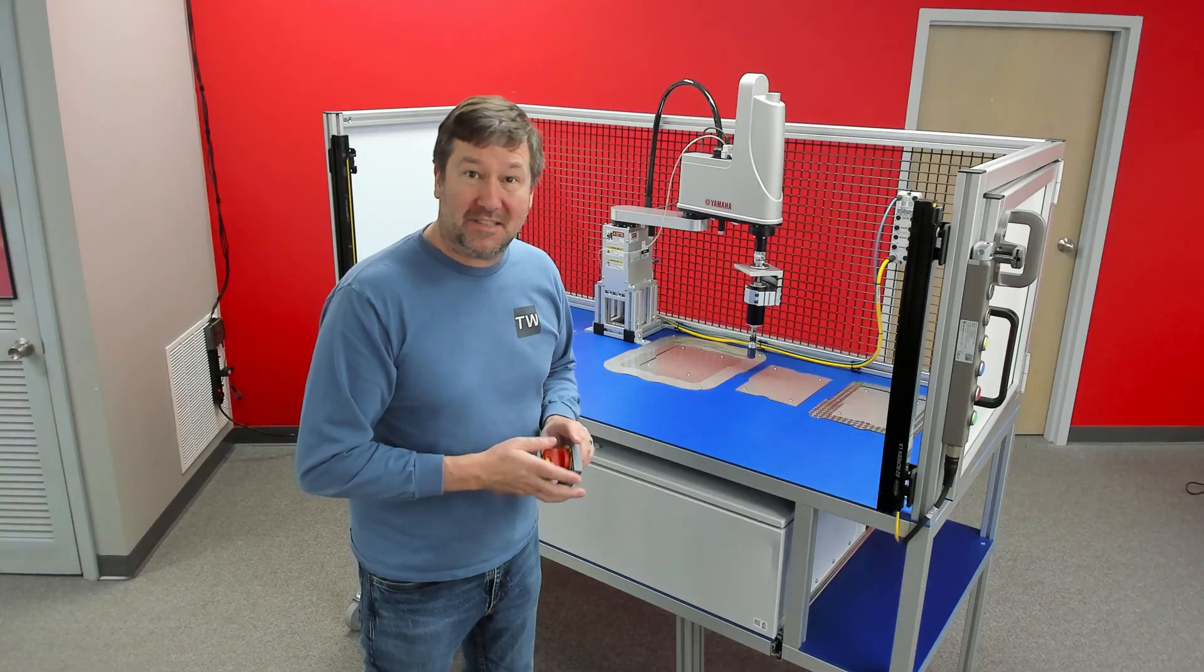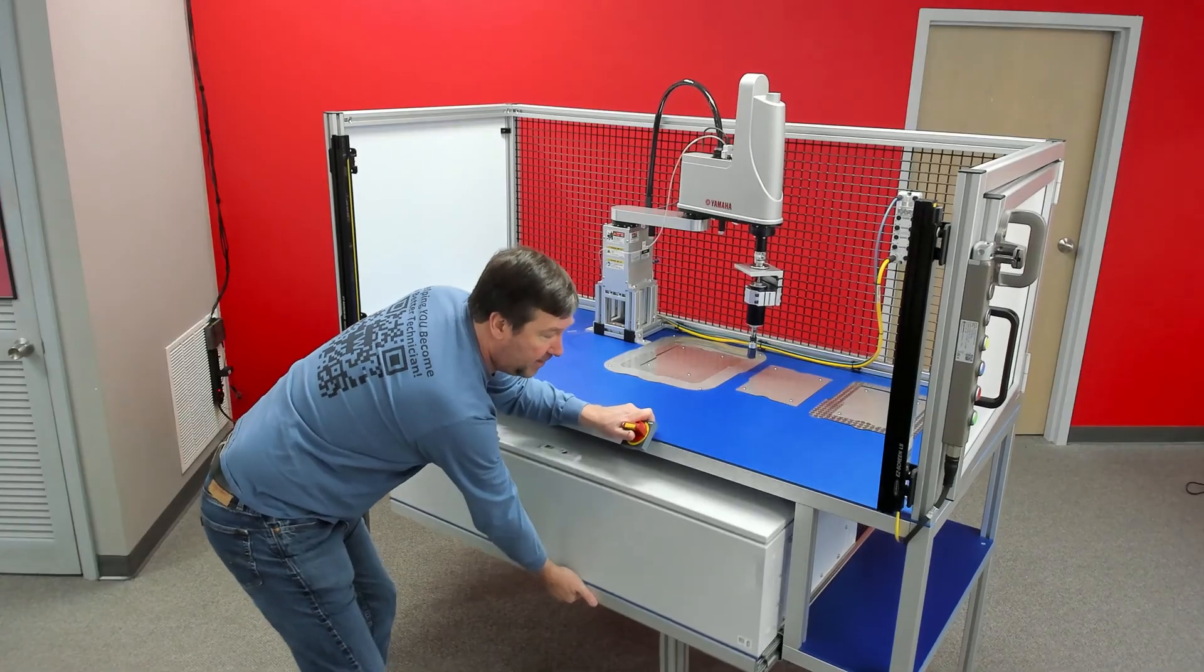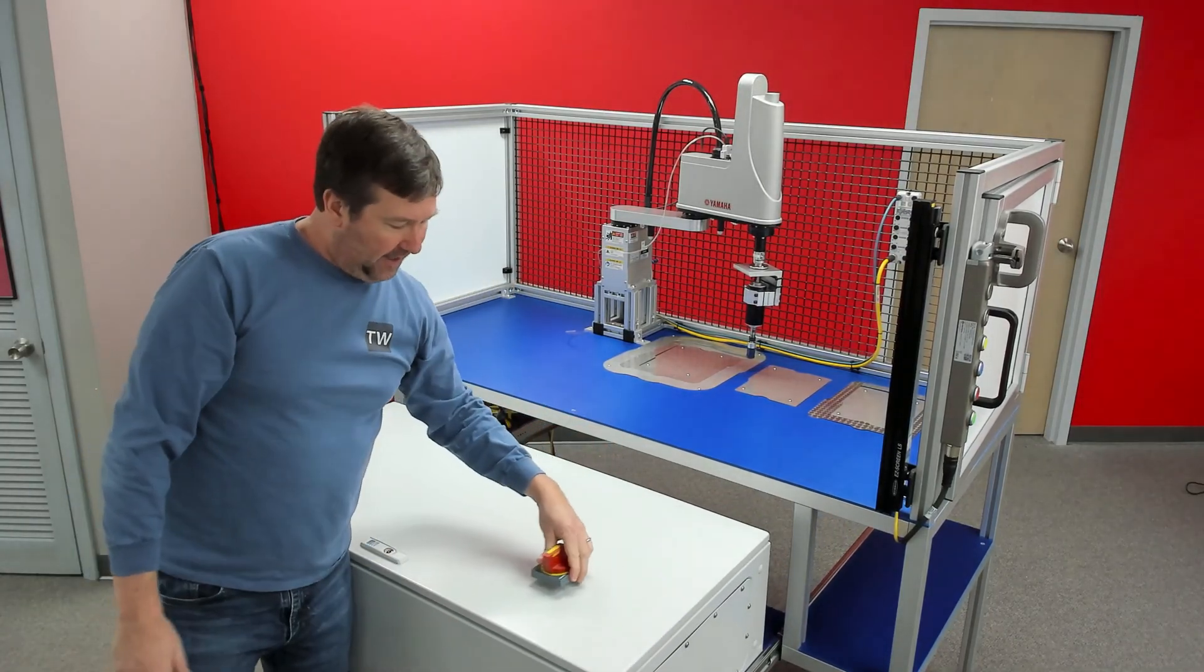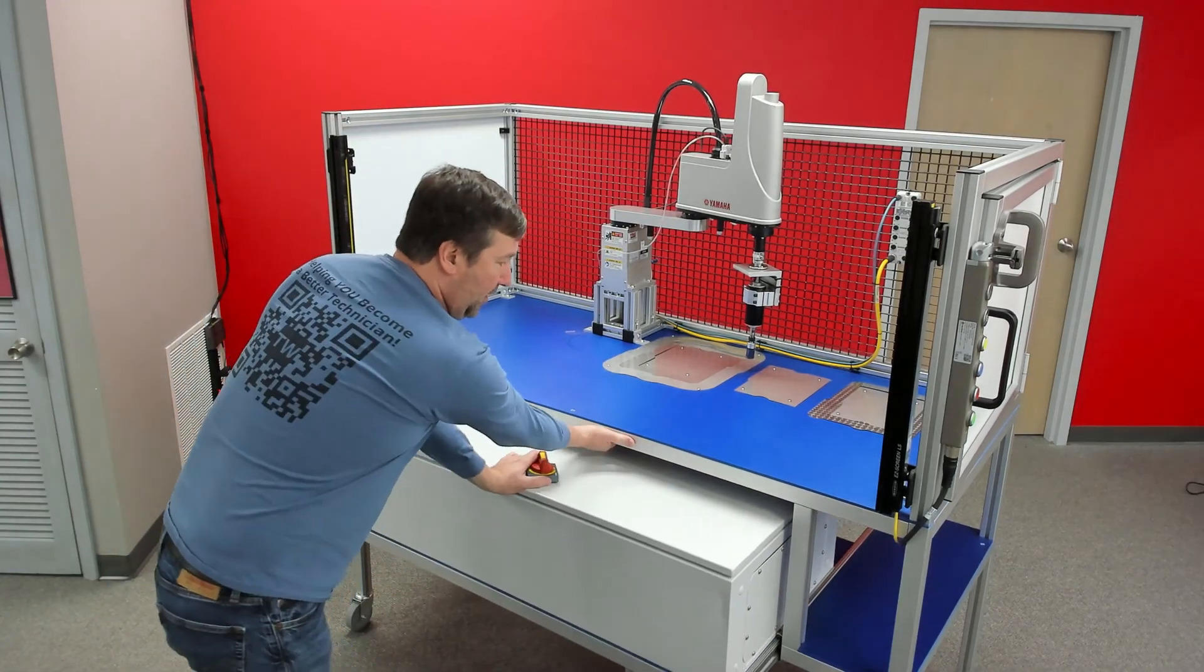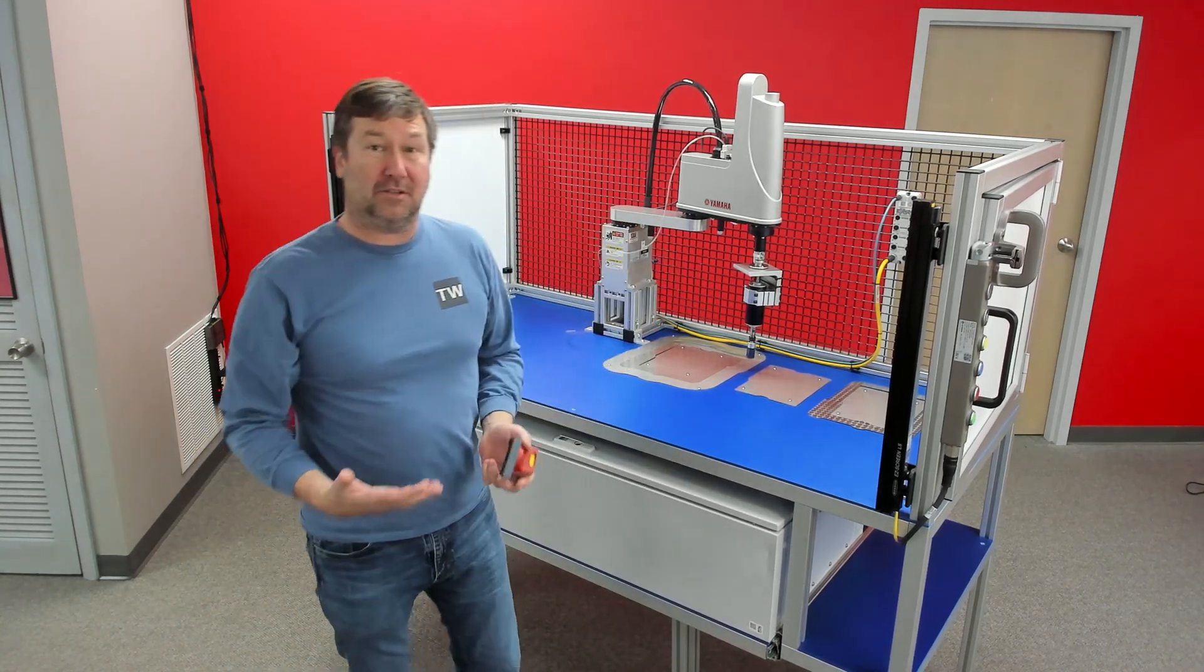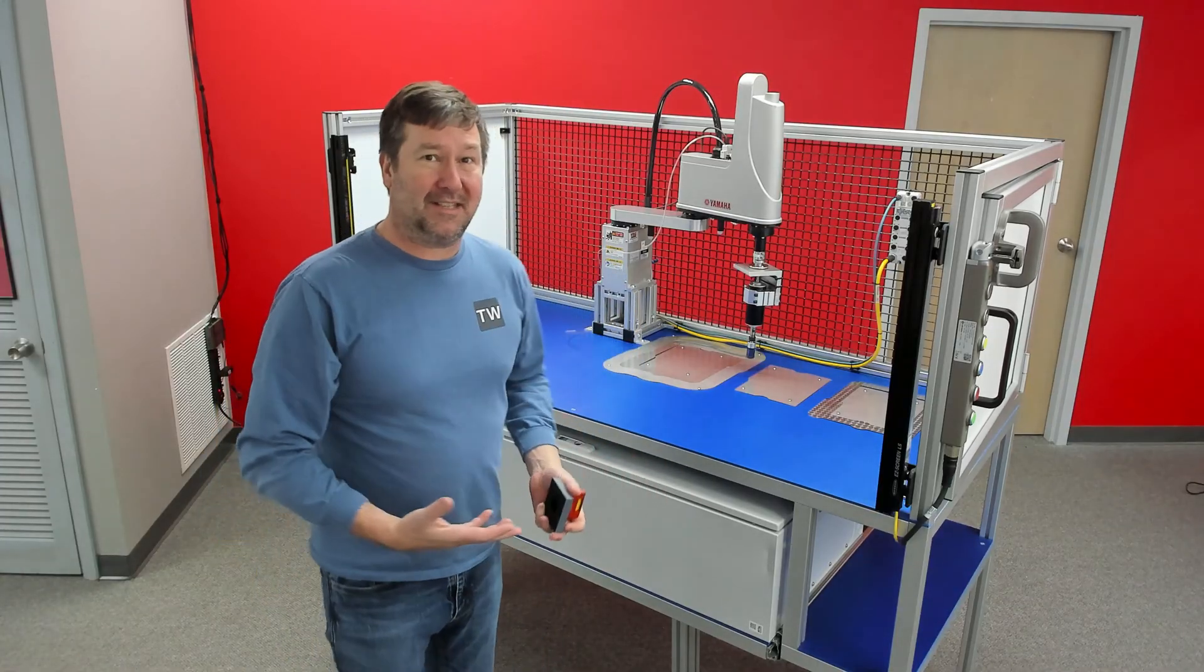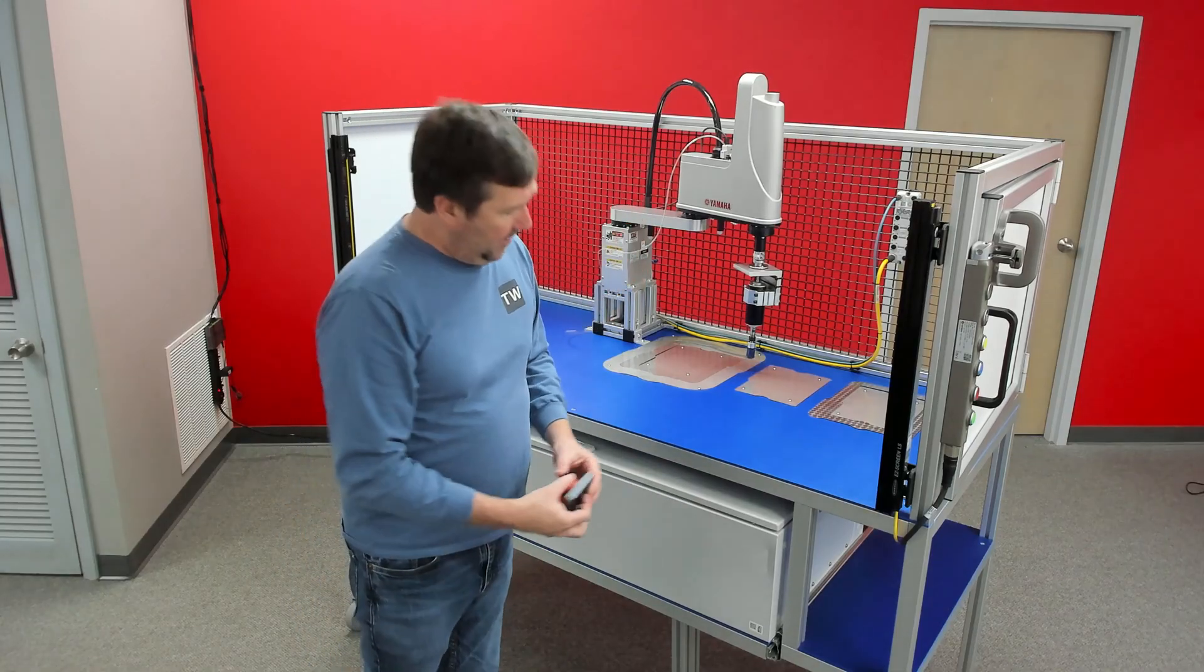First, let's talk about the problem and why I'm doing this. The control panel is on a slide-out drawer, and typically your disconnect will be somewhere around here. If I have it there, when I've pushed it in, then our disconnect is going to be over here where it's difficult to reach. Now, I'm not even going to cite code on this one. We're just going to cite common sense. That's not a good mounting position.